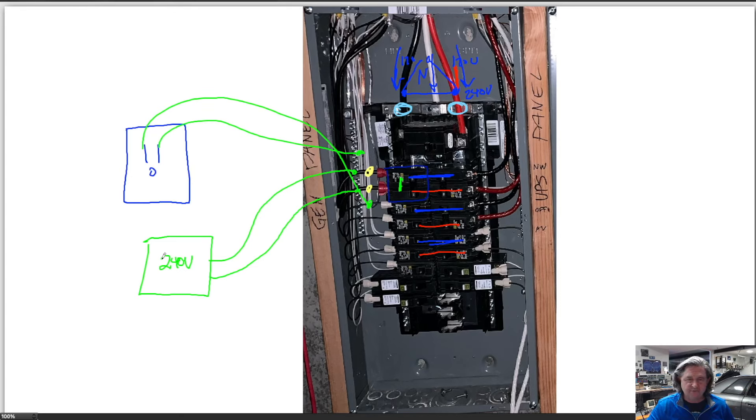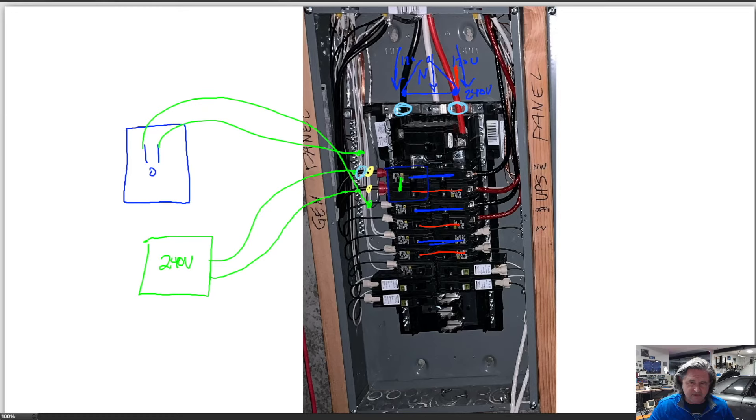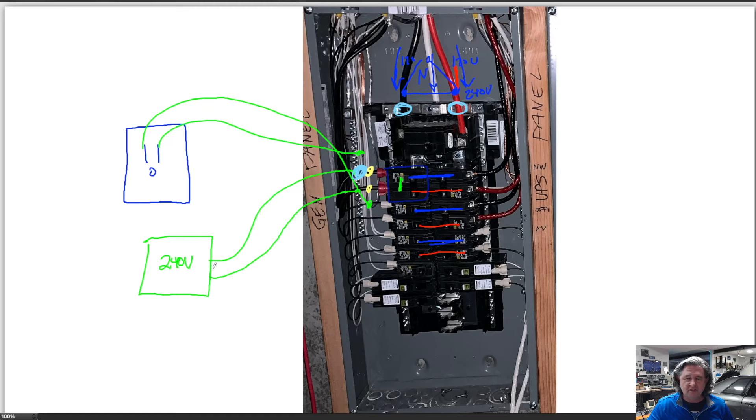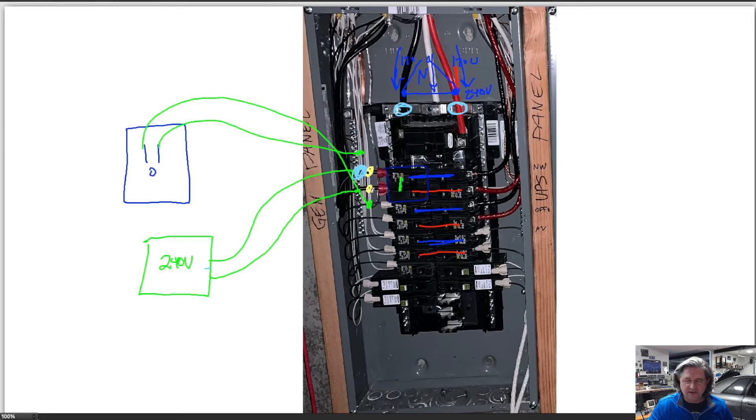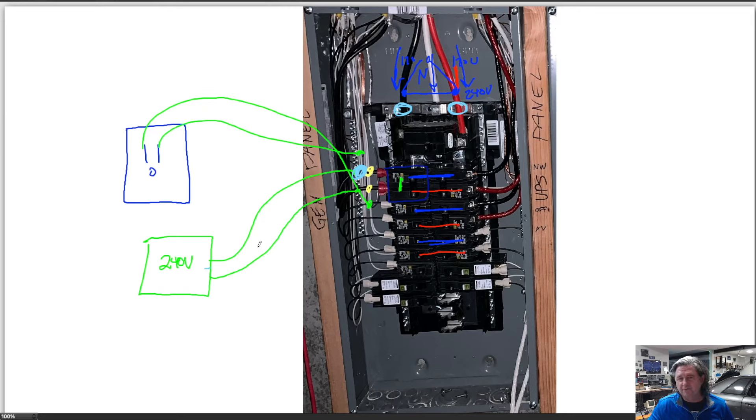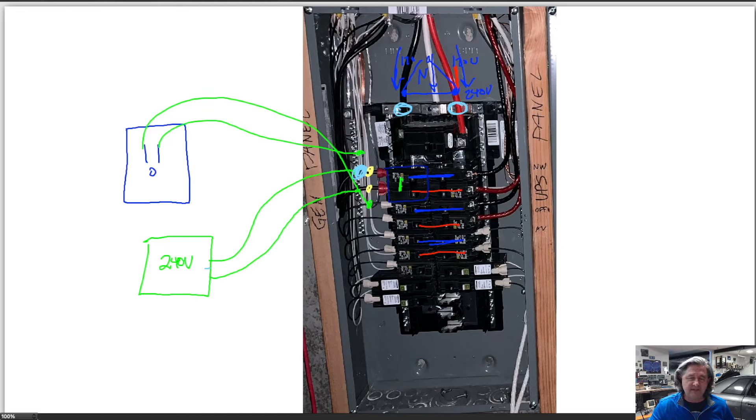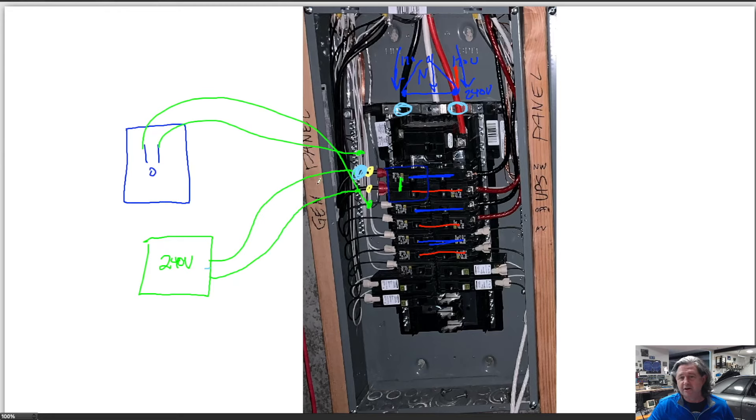Then you can install a CT on every circuit, but if you have a device that is 240 volts you can install a CT on just one of the two wires. Because if there's no neutral coming out of the device then all the current going in one wire has to come out the other wire. So you only need to measure with a CT clamp one of the two legs for a 240 volt device.